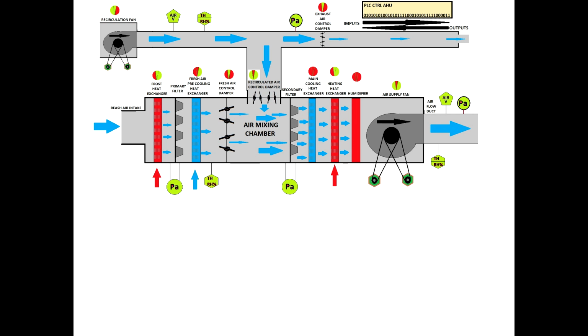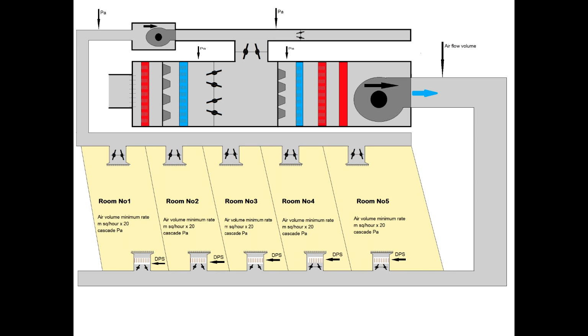You will see further down the line that some technicians have this atrocious pleasure to ignore the automatic control and to manipulate these actuators manually, having great results for a very short period of time, sometimes hours, sometimes minutes, sometimes maybe days. This is very dangerous, because the PLC monitors the system every second. As you will see, it is even hard for me to talk now in this virtual world and to follow how many changes a PLC does to the system to control the humidity, the temperature, and obviously the air volume.